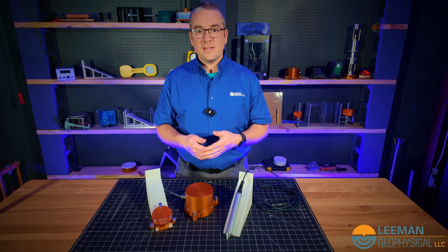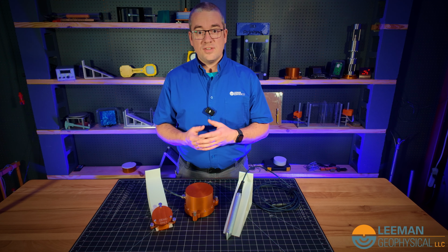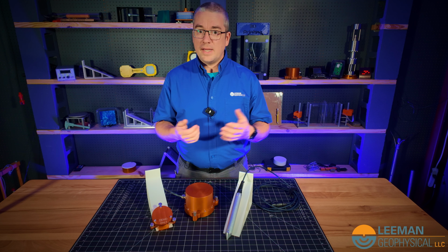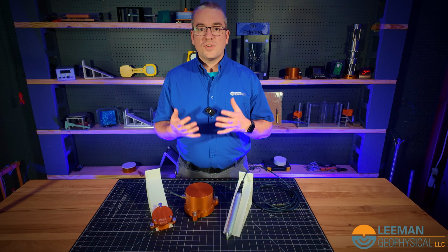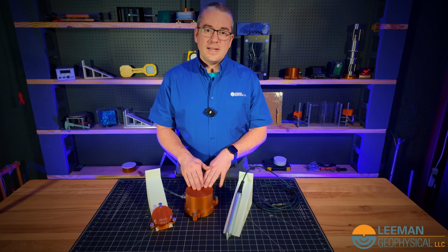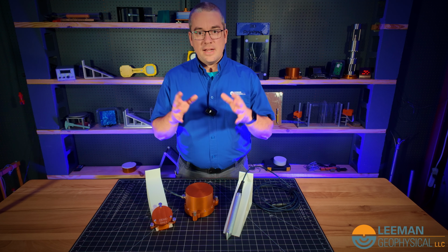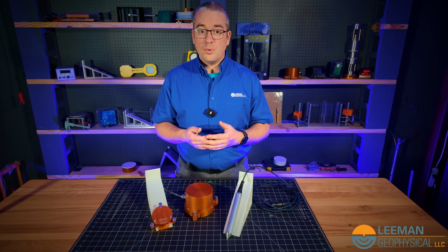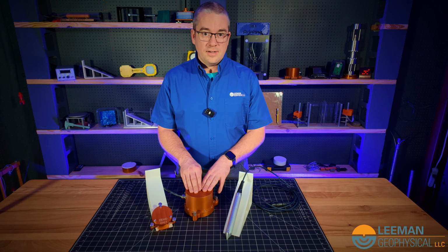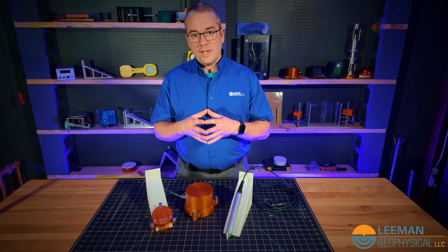We also generally give up some range with the electrolytic sensors. Now we do have electrolytic sensors that go to large ranges for electrolytics, say plus or minus 10 degrees, but the most common application we see when you choose electrolytics is you're getting down into those microradians or nanoradians, and you need a narrower range, say plus or minus 0.3 degrees, which is what this platform tiltmeter in the center is. So it's a much more accurate, but much smaller range instrument.